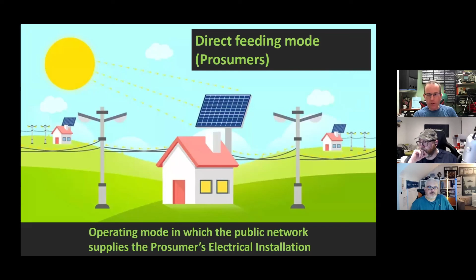It wouldn't become a TT because your supplier references the electrode at the supply end. So it's additional to that until you get to island mode, in which case the earthing type can actually change - because then you are the source, aren't you? So yeah, generally it is connected to the TNCS.